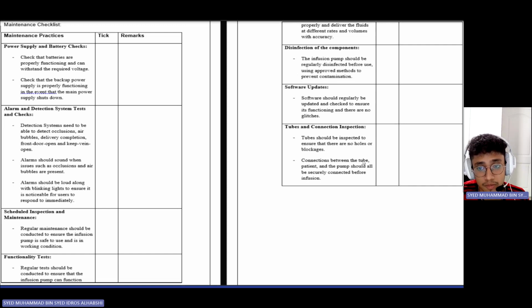Next, connections between the tube, the patient, and the pump should all be securely connected before infusion. This is to ensure that everything flows smoothly and to minimize the risk of any errors occurring, such as occlusion, air bubbles, and so on.